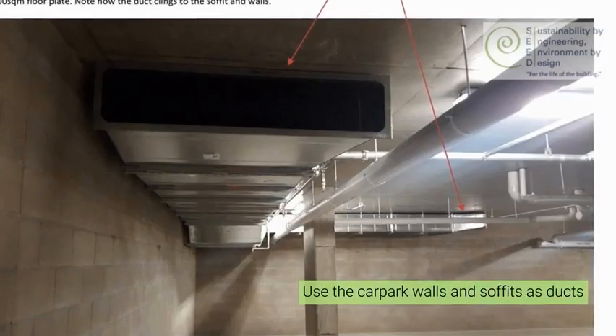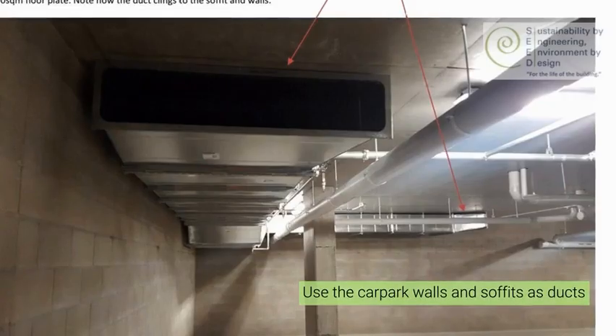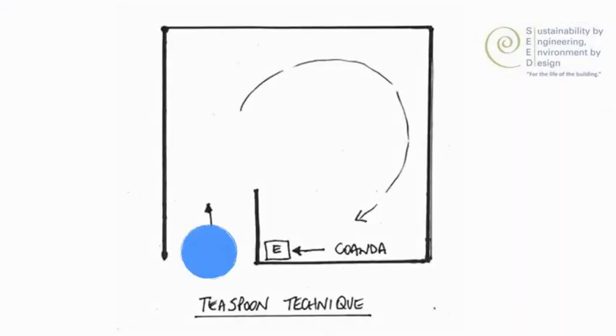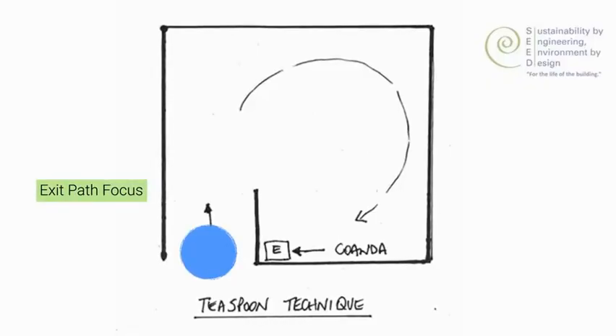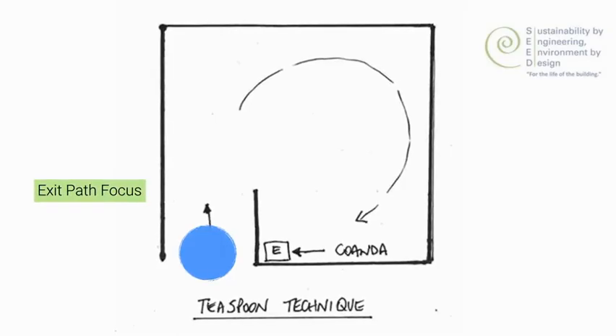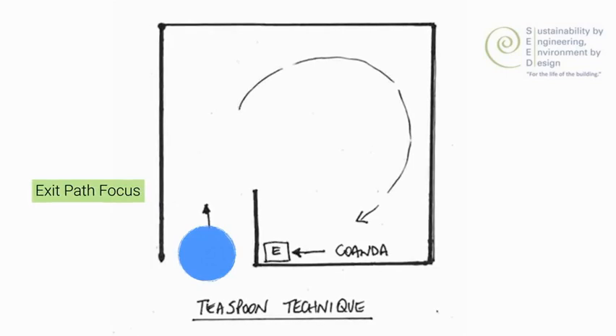Coming back to the exit path focus, by using the exit path carefully, we're able to remove supply air fan systems and establish that swirl. We begin to think of the car park not just in plan view for one floor, but as a stack of floors, and in that manner we're able to seriously diminish the amount of ductwork required throughout the space.